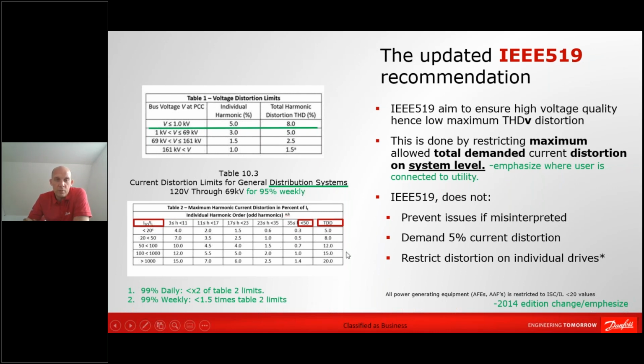What's also important to notice in the standard is that this is for 95% weekly loading. So you are allowed short-term peaks. If you have something that loads the transformer more for a very short period of time, that could be a run-in situation, or a short-term overload of your transformer where you need to loosen up a tension or something, then that is allowed in your installation and still complies with IEEE 519. So we're not talking about overload situations, we're talking about normal running conditions. There are also some specifics on how much extra you are allowed. You are allowed up to 2 times the values for 99% of the daily loading profile.